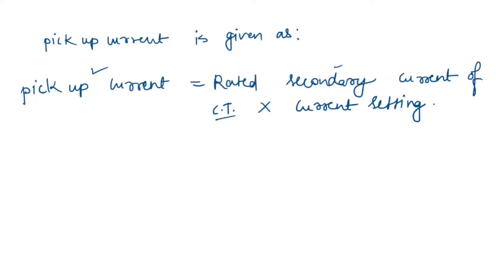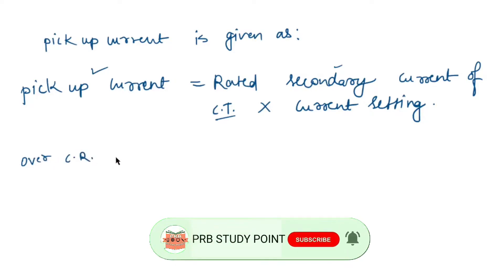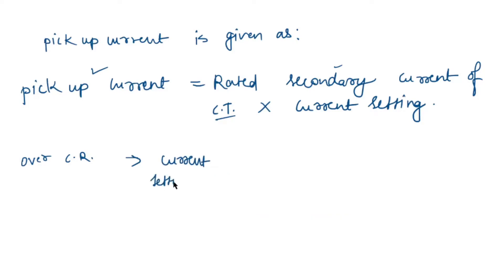For example, consider an over-current relay having a current setting of 130%. It is connected to a supply circuit through a current transformer of ratio 400 to 5.